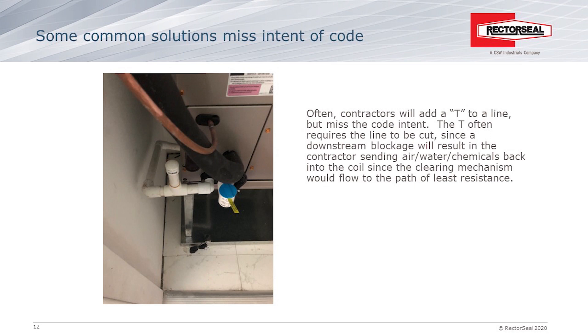The new drain line maintenance code states: drain lines shall be configured to permit the clearing of blockages and performance of maintenance without having to cut the drain line. What's happening out in the field now is a misconception about the intent of this code. Contractors are installing PVC T-fittings in the drain line, or pieces of clear hose, or couplings or unions — and it's missing the intent of the code.